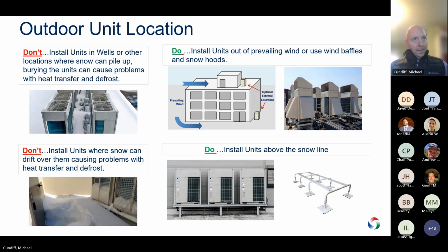So to fix this, on the top right, do install units out of the prevailing winds or use wind baffles and snow hoods. And we say out of the prevailing winds, I don't think anybody expects anyone to have a windsock, making sure these things are on the leeward side of everything. But some thought should be put into it, especially if you have units that are completely, totally exposed on a roof with 40, 50 mile an hour winds in the middle of a snowstorm. Obviously that's going to affect performance a bit.